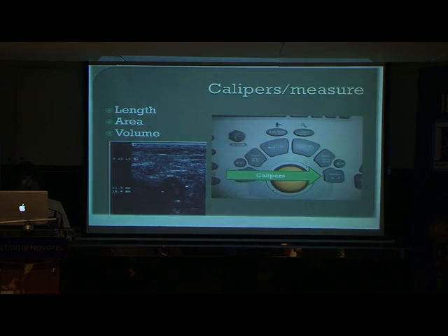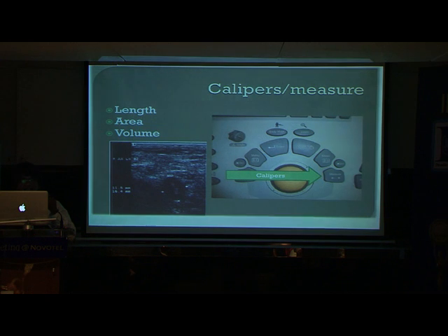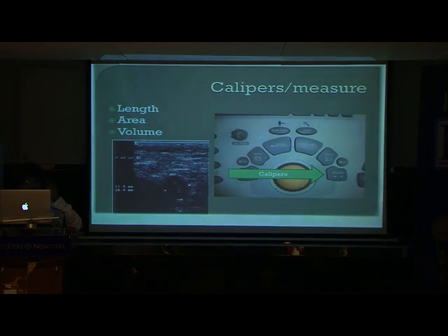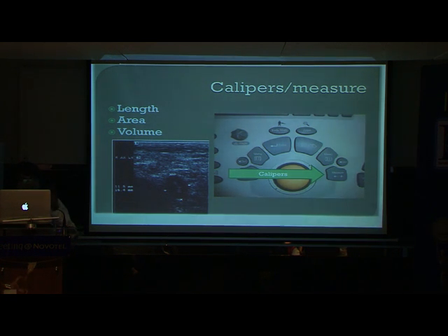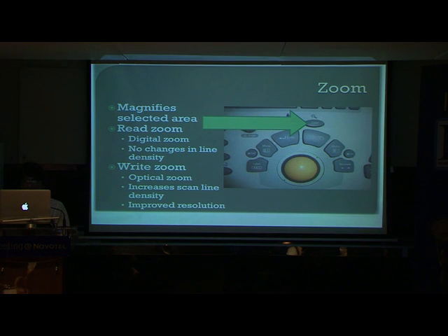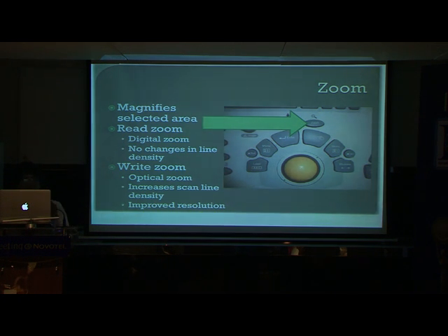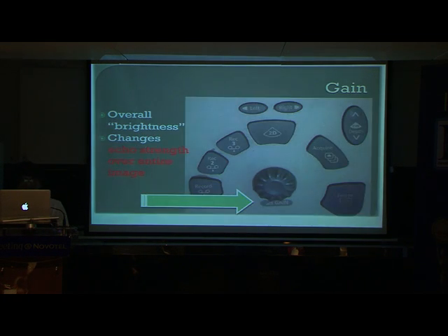Always take measurements — whenever you are on a target organ and need to measure it due to standard variations or anomalies. Make a habit of measuring length, area, and volume. You can also zoom the image using a button just above the trackball. All these tools are used to optimize image quality, get the area of interest in the field of view, and perform the intervention safely.